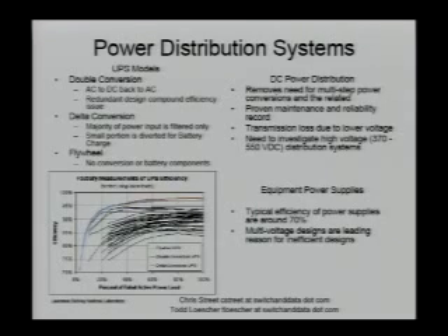Looking at these different UPS models, Lawrence Berkeley did a research paper on this, I think it came out last year, or maybe '06, that shows this. On the x-axis you see the active power load across the UPS, and efficiency on the y-axis. As you can see, they all pretty much share the same kind of efficiency at low total UPS load. So you want to make sure you're loading your UPS effectively, with enough power load across it. As it gets up higher, that's where you'll see the differences.